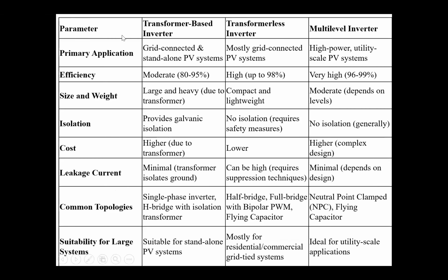These are the parameters compared across transformer-based inverter, transformerless inverter, and multi-level inverter. Mainly, efficiency: the transformer inverter has 80 to 95% and the transformerless inverter has up to 98%. The multi-level inverter has 96 to 99%. Mostly, multi-level inverters are used for high power applications.